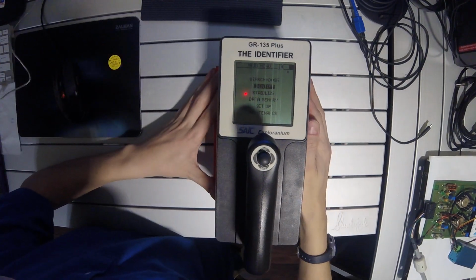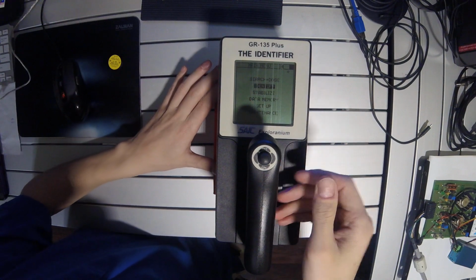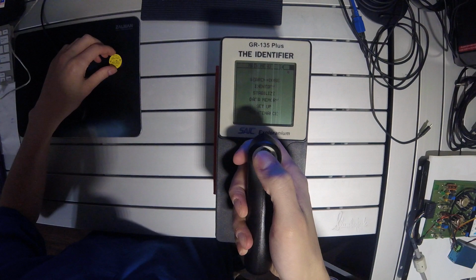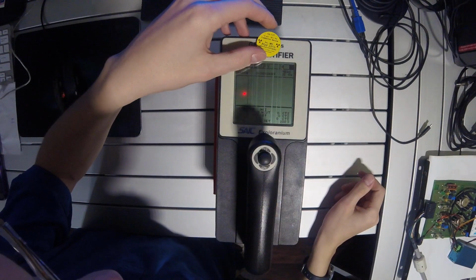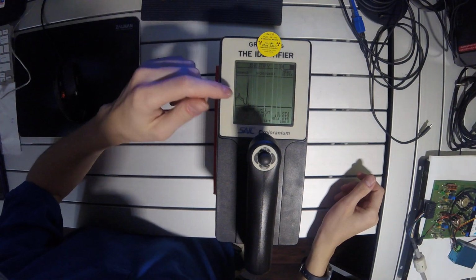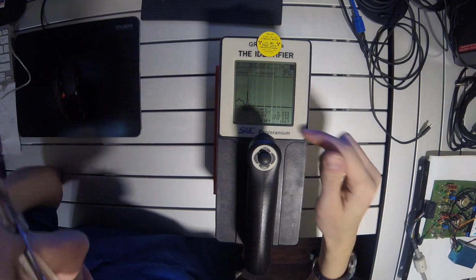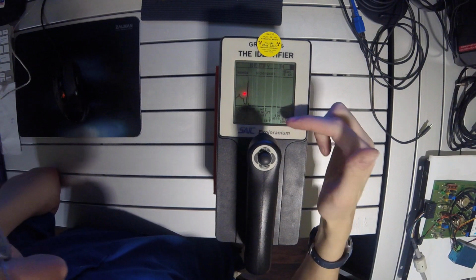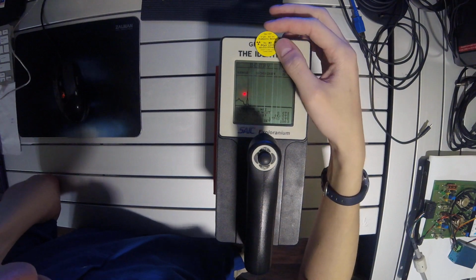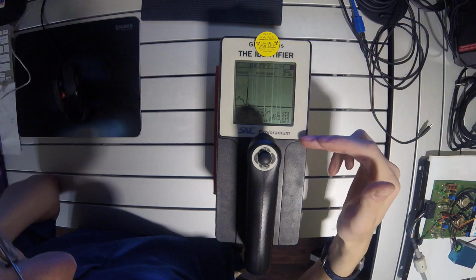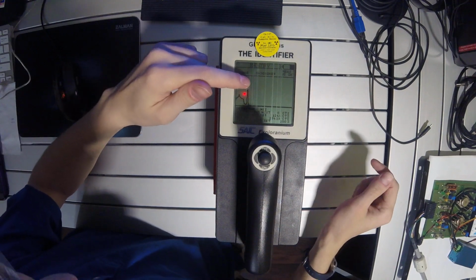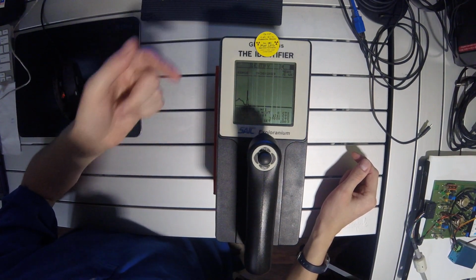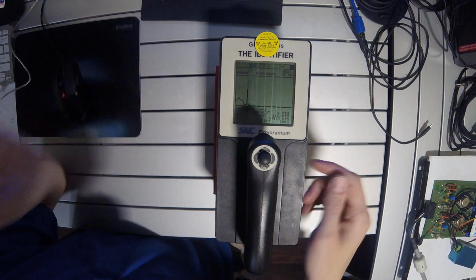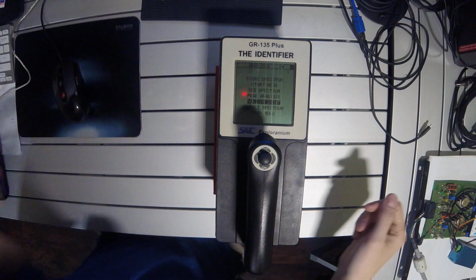The next feature of this unit is you can actually identify gamma ray spectra and identify radioactive isotopes. So selecting identify mode, now it's starting to build the gamma ray spectrum here. It'll also put out a readout for neutron counts if any neutrons are detected. In this case, it's just a cesium-137 gamma ray source, so it will not be detecting any neutrons. We can clearly see the main peak forming. Right now it's set up for 200 seconds of counting. However, since it's a pretty strong source, it has an adequate spectrum now, so I'm just going to cancel the accumulation by hitting enter again.